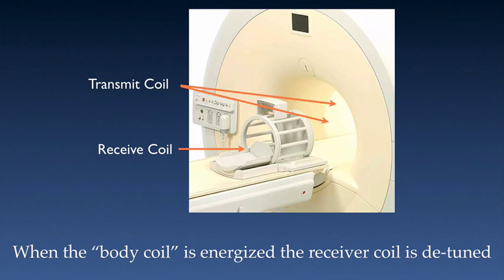When using a receive-only coil in a cylindrical bore high-field magnet, the integrated body coil is going to be used as the transmit coil. When the body coil is energized, the receiver coil is detuned by the system software so that it doesn't have current induced in the coil during RF transmission.